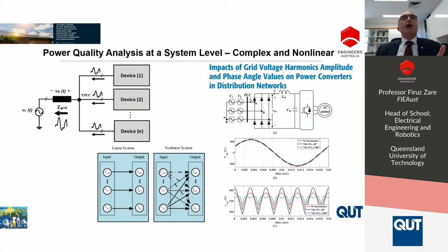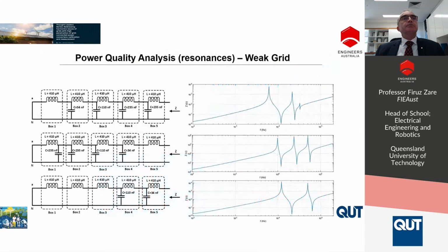That's why it is important to identify that when you buy a power electronic device, that device is tested at the device level under more or less sinusoidal conditions. But when those devices are connected to a distorted grid, we expect much more harmonic current from those devices, depending on the background harmonics. So I want to clarify that the system analysis is completely different from device-level analysis, and that's why the harmonics and interaction in the network will be different.